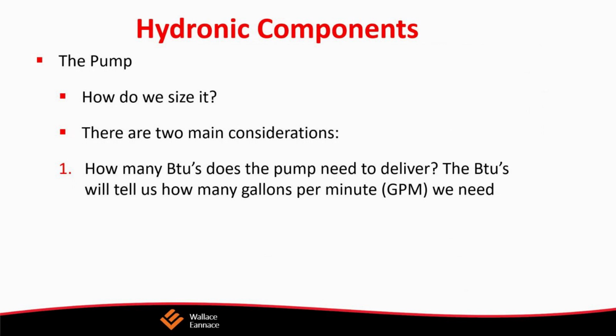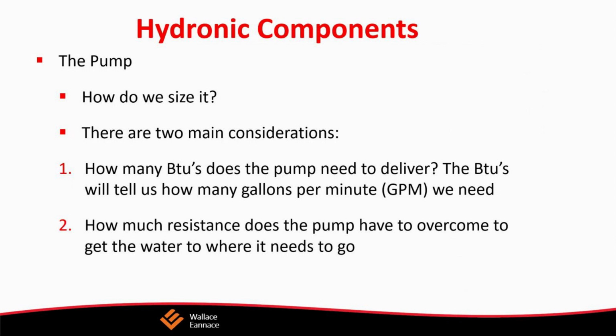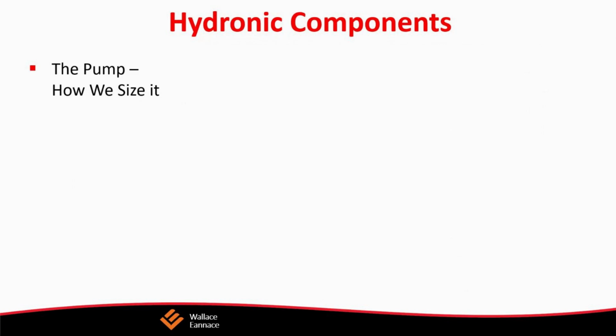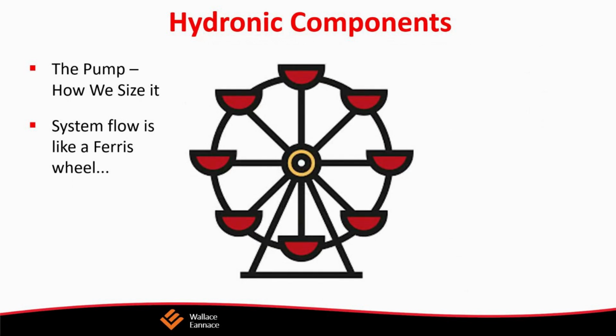That is my delta P. Now I have to convert this to feet of head by using the constant. 8 times 2.31 equals 18.48. We can round this up to 18.5. Now we find 18.5 on the foot head side of the curve, and we make a mark. Then we draw a straight line from this mark toward the impeller curve. Once we contact the curve, we change direction, and we start heading toward the GPM side of the curve. Your GPM is determined by the point where the line intersects the GPM side of this curve.